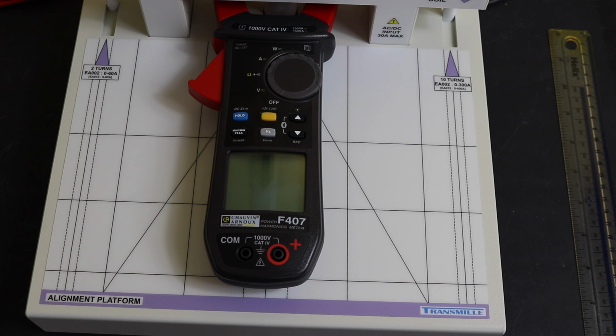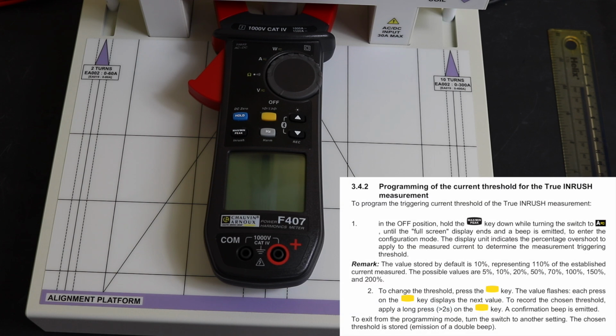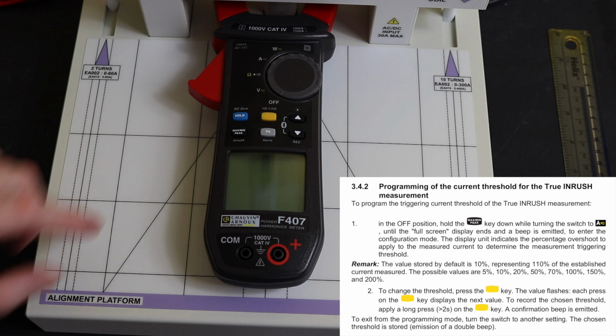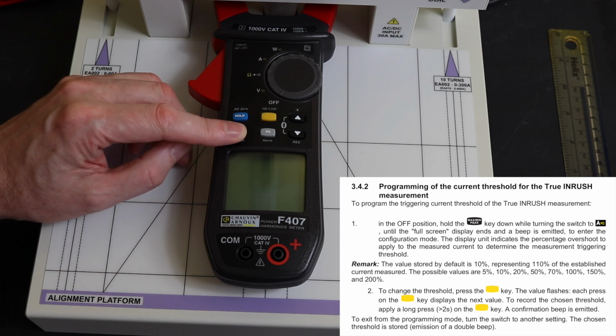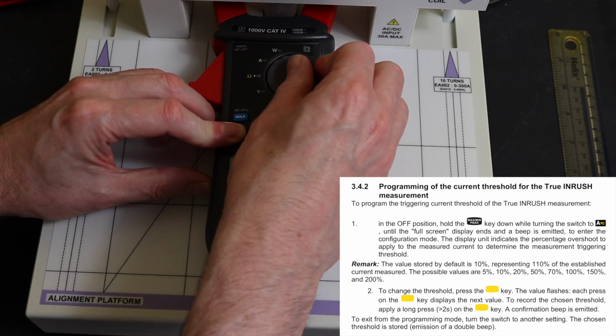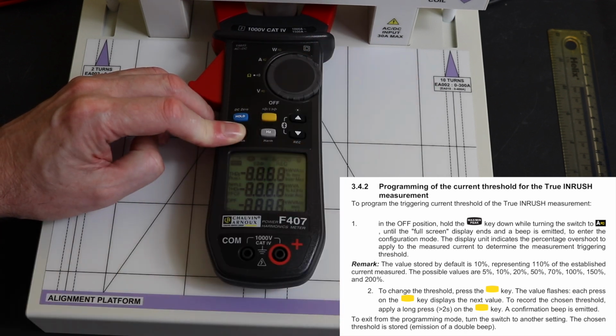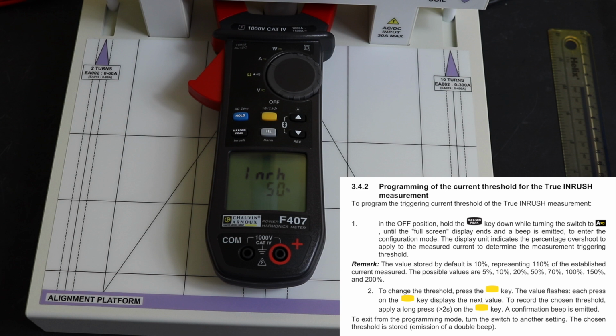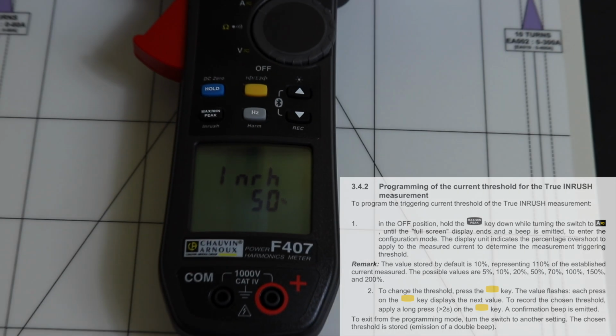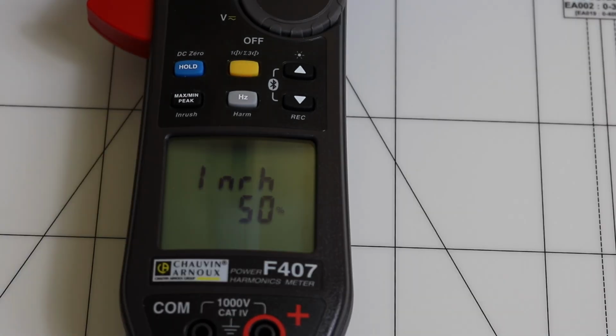Just before we turn the instrument on, the inrush function does have a threshold trigger to it, and to get to that you actually have to hold down the maximum peak button once you turn the instrument on and turn it around to the amps. Wait for it to beep. There you go, and there you see inrush. Zoom in there, hopefully. See it's flashing away there, 50%.